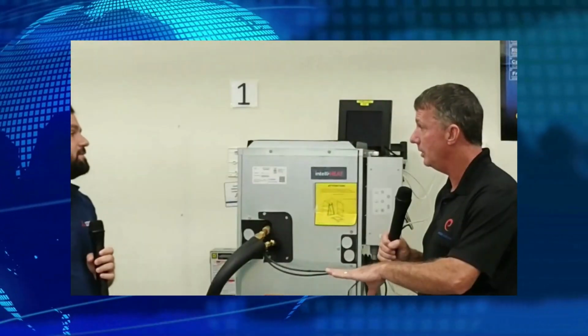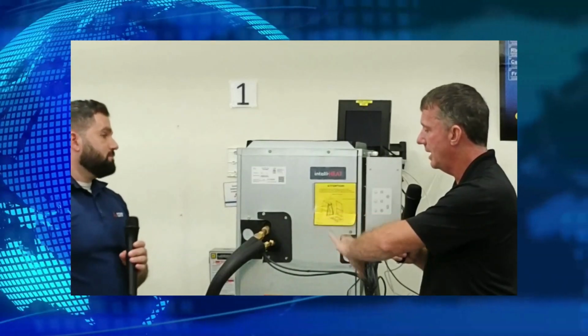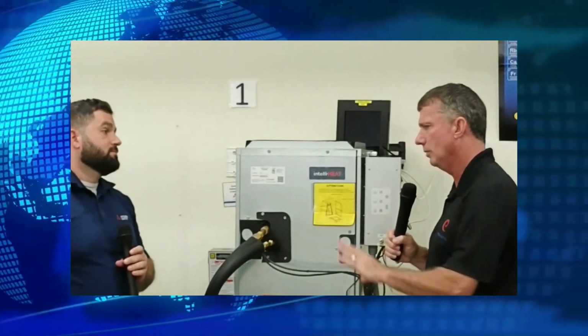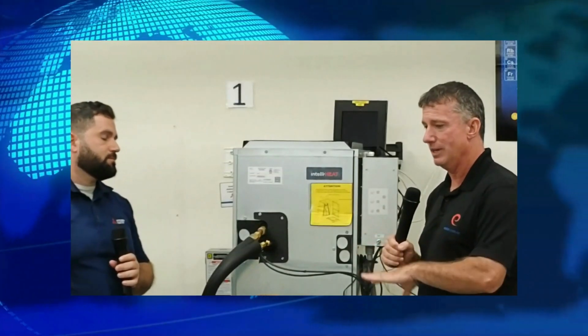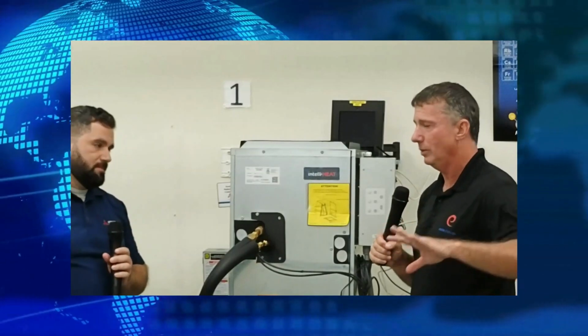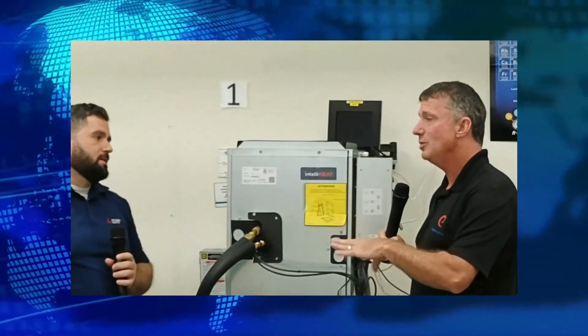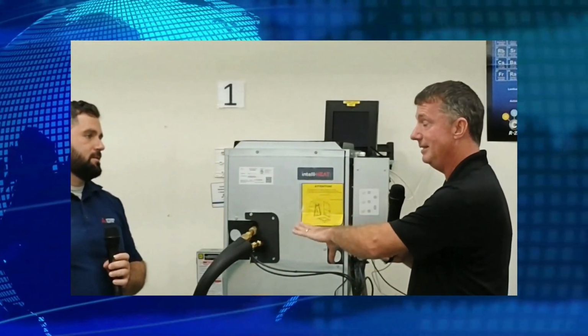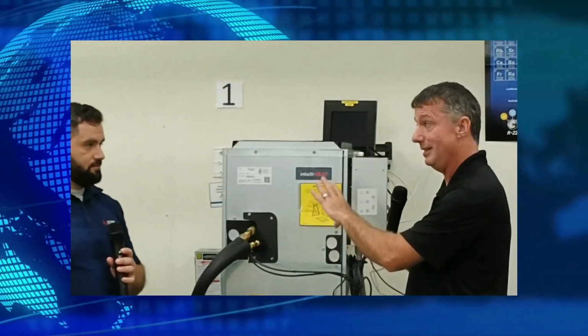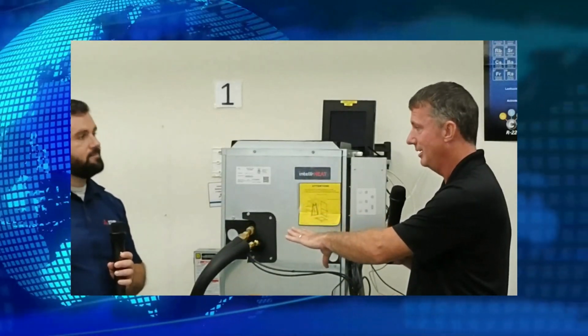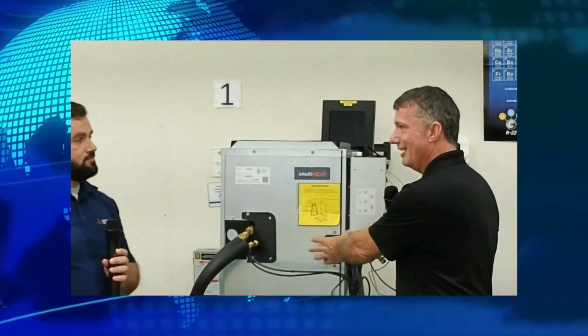Inverter technology - we're able to hook up that inverting outdoor unit and actually attach it onto a cased coil. That's a little different than we've thought of in the past, because on a typical residential heat pump application we're using a traditional cased coil with an outdoor unit. But since we're talking about a ductless-style outdoor unit that has the expansion valve, the LEV, at the outdoor unit, we actually don't even have a metering device in this coil because it's managed by our outdoor unit.